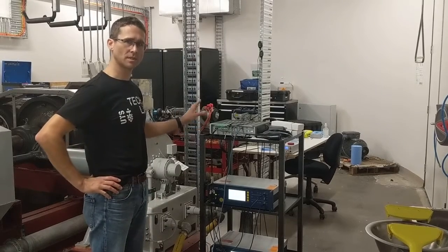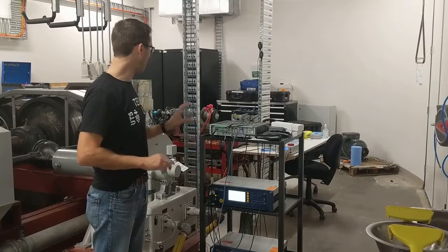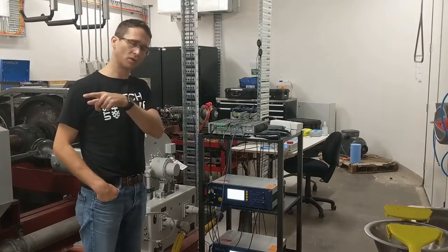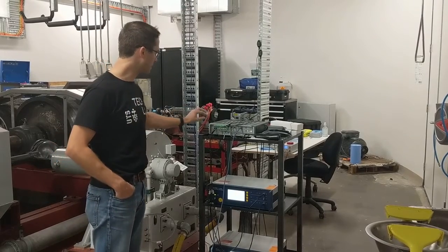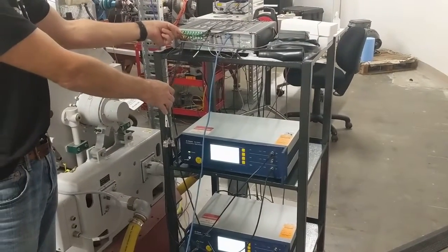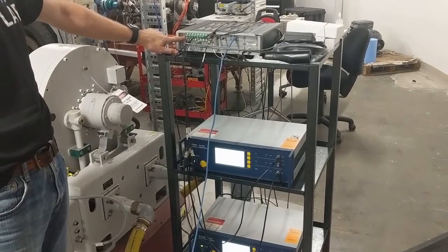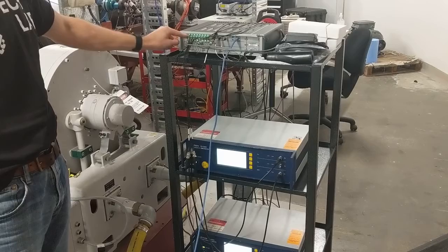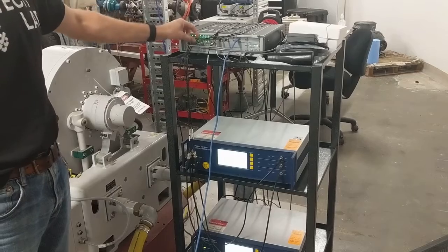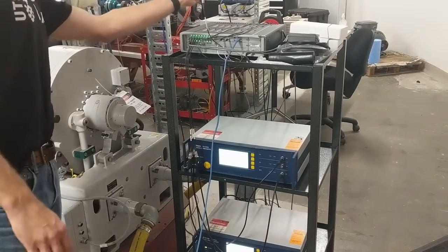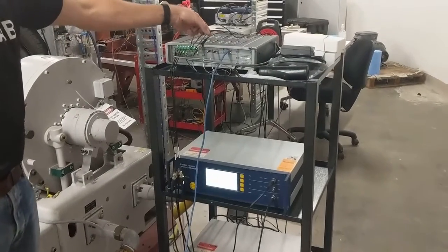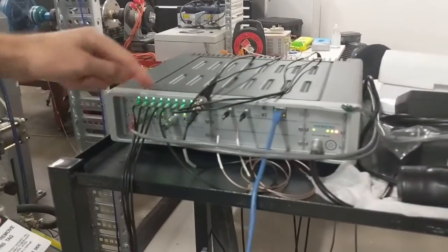On this trolley, which is deliberately positioned away from our experimental setup, such that we can see the front panel from the control room through a glass window, is our acquisition system. Here you can see we have multiple sensors connected into the acquisition front end onto an input module. We have our 2 laser vibrometers coming in on channels 1 to 4, and I'll show those in more detail. We have, I believe, our torque transducer connected into channel 5, and we have our 3 accelerometer directions onto channels 6, 7 and 8 of our acquisition system.